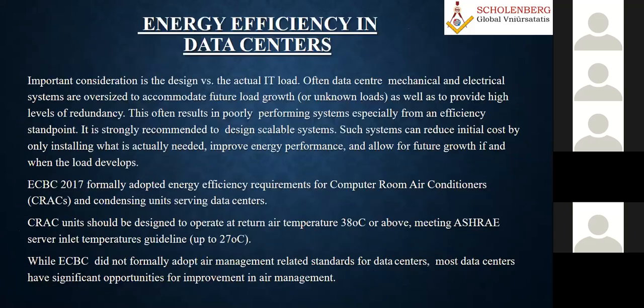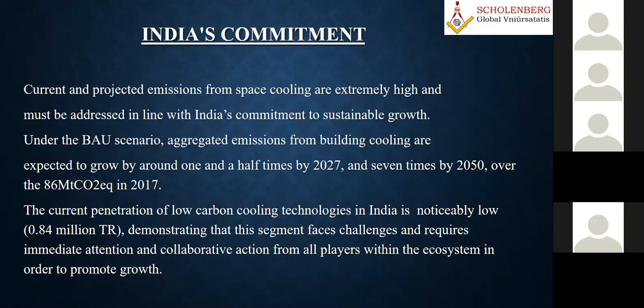My question was, suppose I'm having a dedicated outdoor air unit. Okay. And with that, I'm supplying air that is just the outdoor air to certain zones. Mm-hmm. And instead of supplying the air neutral at 75 Fahrenheit, I have planned to supply it, say, at 47 Fahrenheit or something, 47 or 48.